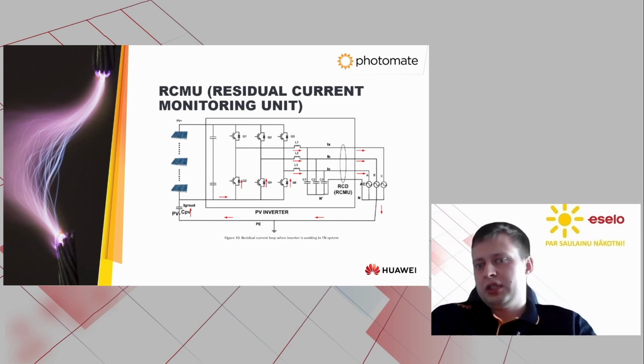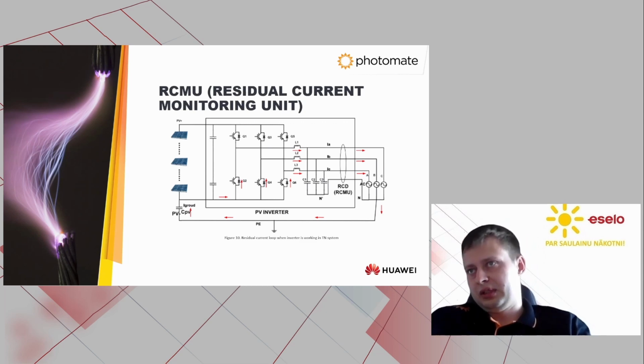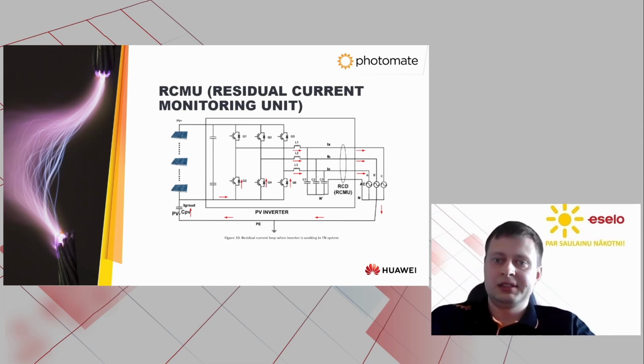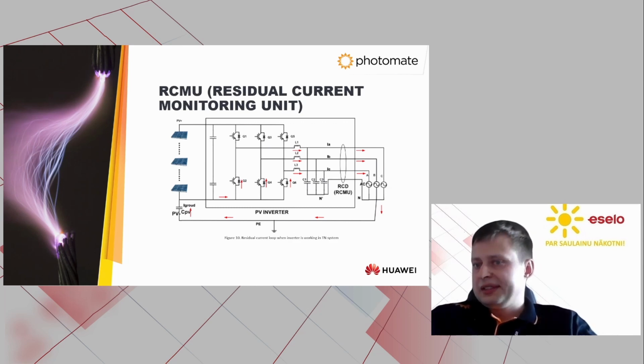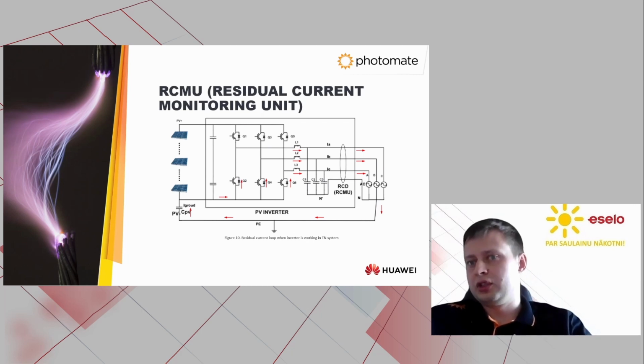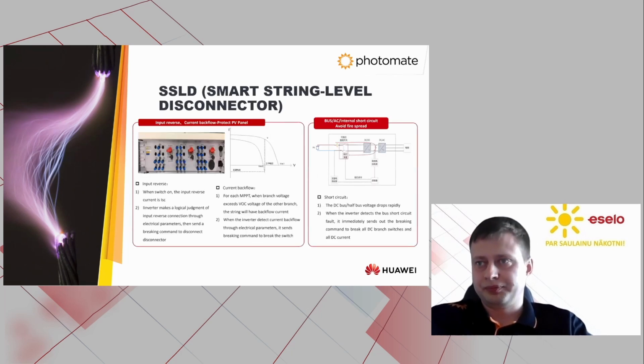So to avoid this situation, to keep this current within normal limits, Huawei has the RCMU, which means Residual Current Monitoring Unit. During operation, the inverter continuously monitors residual current in real time. If the RCD sensor detects any leakage current that flows through the ground and around the inverter, it trips the inverter to avoid additional problems.